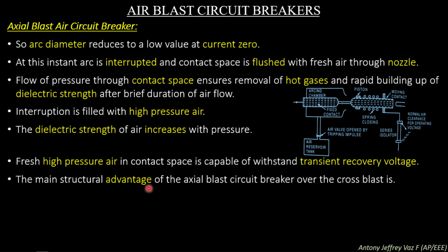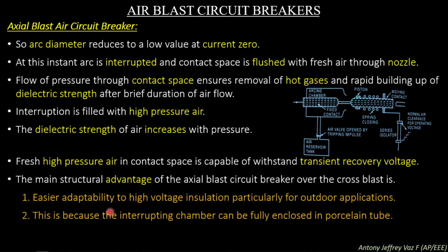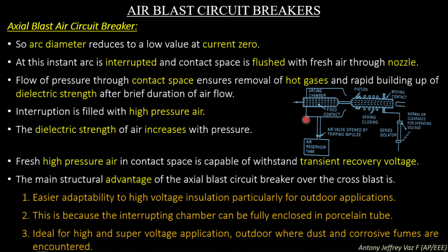The main structural advantage of axial blast circuit breakers over cross blast is easier adaptability to high voltage insulation, particularly for outdoor application. So axial blast air circuit breakers can be used for high voltage applications and can be placed outdoors. This is because the interrupting chamber can be fully enclosed in a porcelain tube. So the complete interrupting chamber, which is the arcing chamber, is insulated through a porcelain tube.